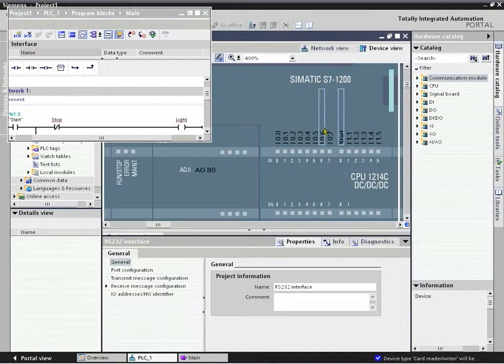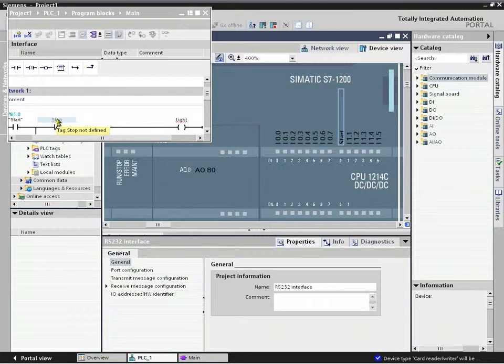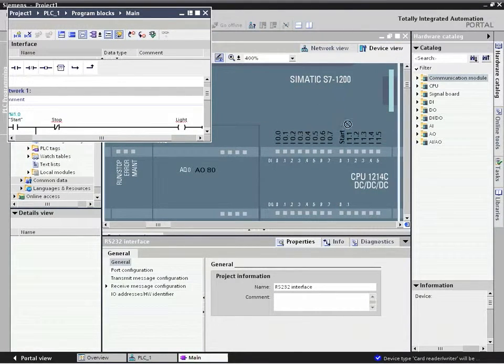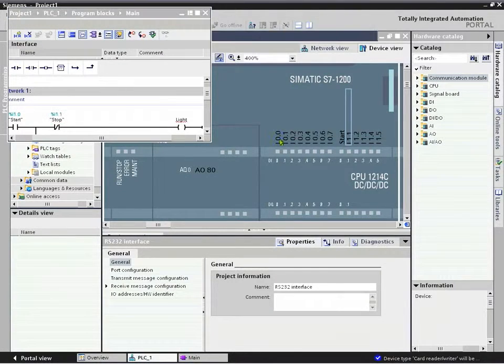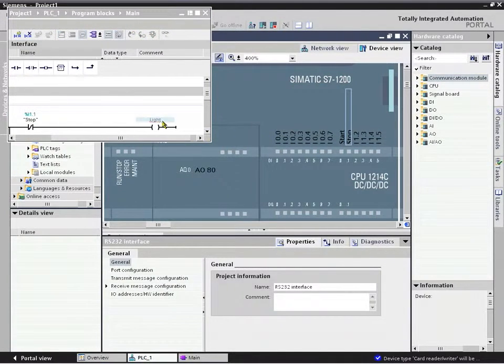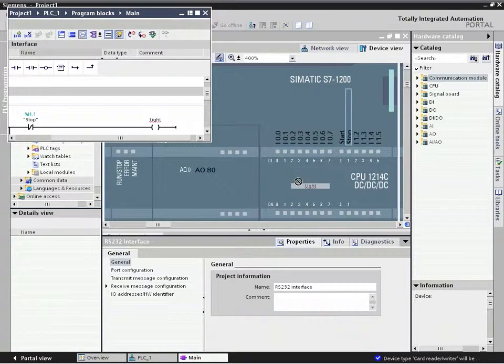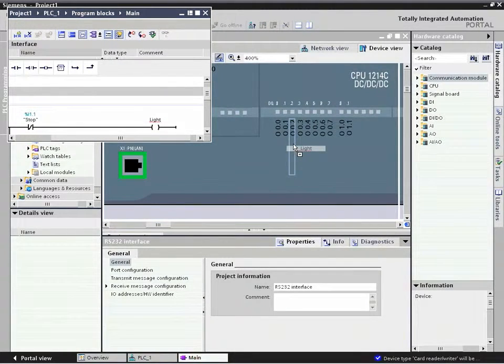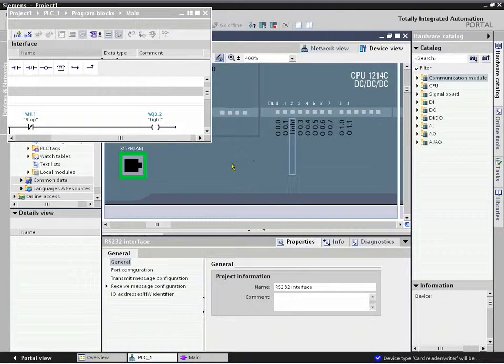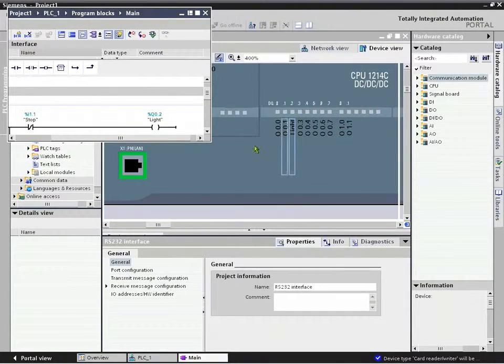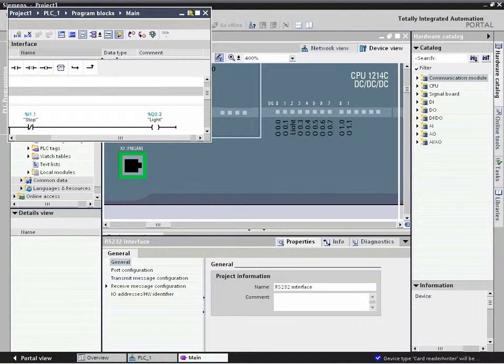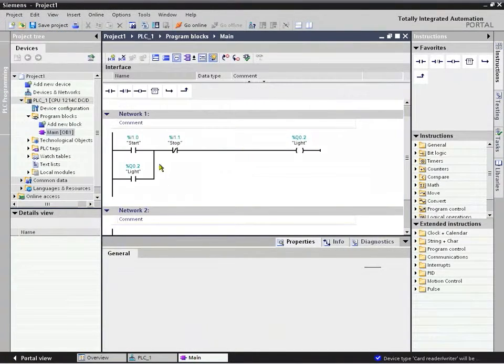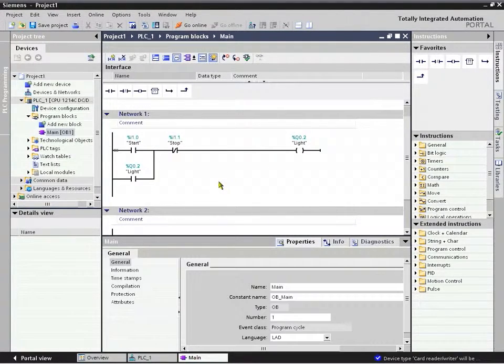And I don't need to know what the address is there or is it I's, is it O's, is it X's or Y's. Same thing with my stop. I know if I have it wired to that second terminal on that bank of inputs. And then with my output I'm going to bring it right over to this, which is the third output in that particular bank of outputs. So I was able to bring over these elements right to my IO configuration without opening a manual, without having to figure out what the syntax of the addressing. And then it aligned the real addressing with my tag elements and populated my tag database.